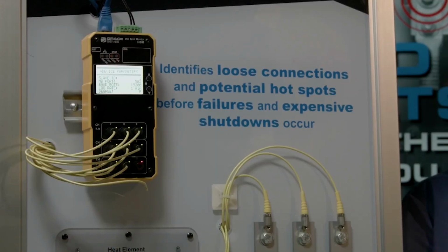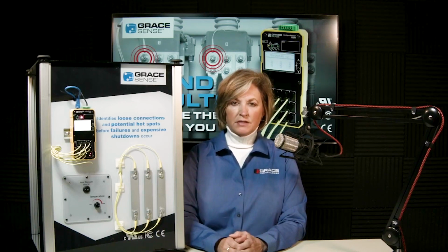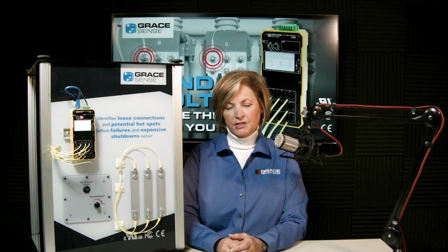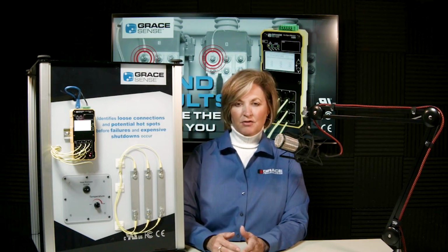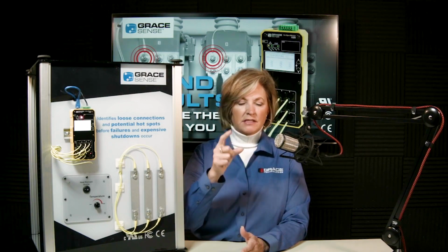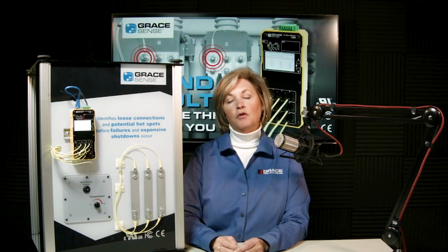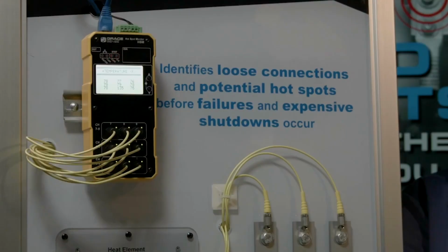In low voltage equipment and switchgear, for example, it is often hard to get a thermal scan on a riser of cable connections from low voltage switchgear. So getting those cable terminations in switchgear would eliminate the need to try to bob and weave behind the different connection points going to the different low voltage breakers. So those cable chimneys are definitely in the way. So getting those monitored would be great. Low voltage motor control, again, this can route with power cables and comm cables. So anywhere within the low voltage equipment could easily be monitored as well.